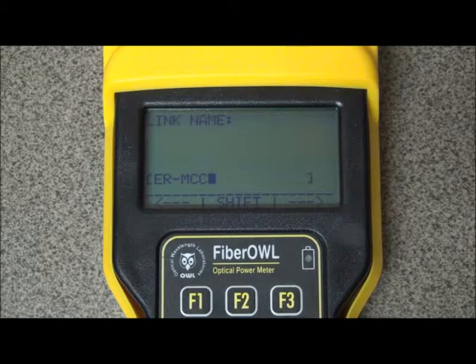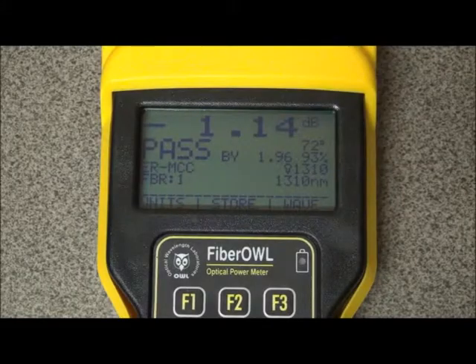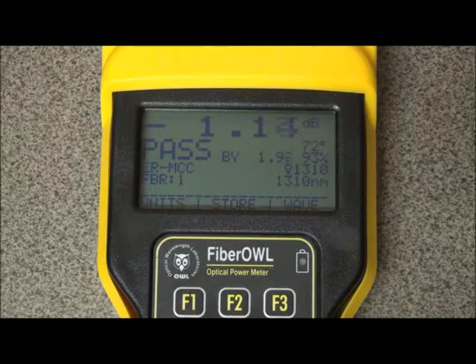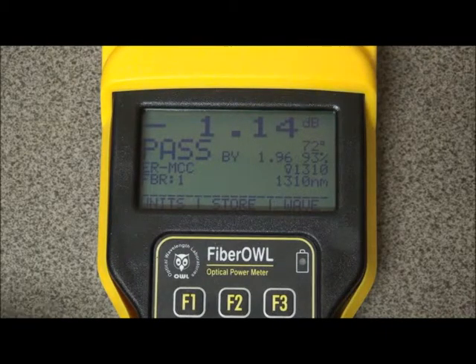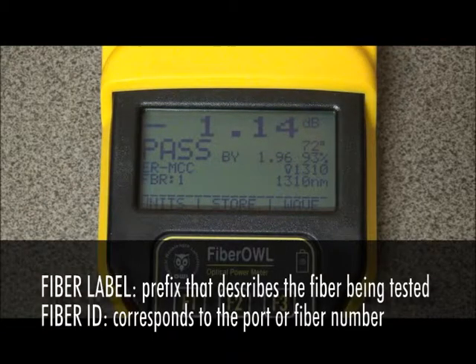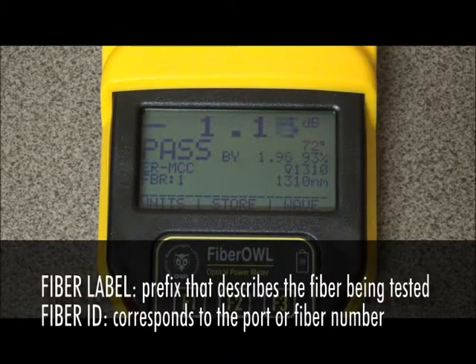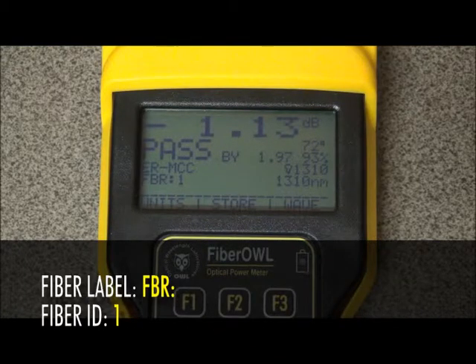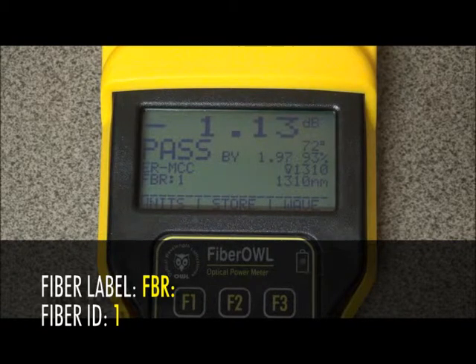The next two parts of fiber naming occur when storing test results in the optical power meter. Here we see a typical screen when taking a reading. A typical fiber name might look like this — as you can see on the screen, it says FBR colon 1. This name consists of two different parts: the fiber label and the fiber ID. The fiber label is a prefix that further describes the fiber being tested, and the fiber ID is the port number or fiber number. In this case, the fiber label is FBR colon, and the fiber ID is one.